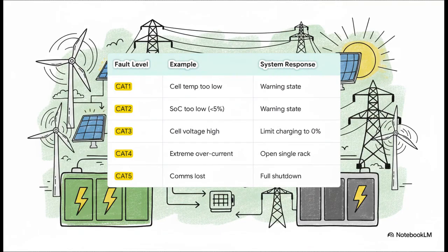This table shows how intelligent that system is. A low-level Cat 1 fault, say a battery cell gets a little too cold, might just pop up a warning. But as the problem gets more serious, the system's response escalates. A Cat 3 fault could automatically stop the battery from charging to protect it. All the way up to a critical Cat 5 event, like losing communication with the grid, that triggers a full but safe shutdown of the entire system, all on its own.